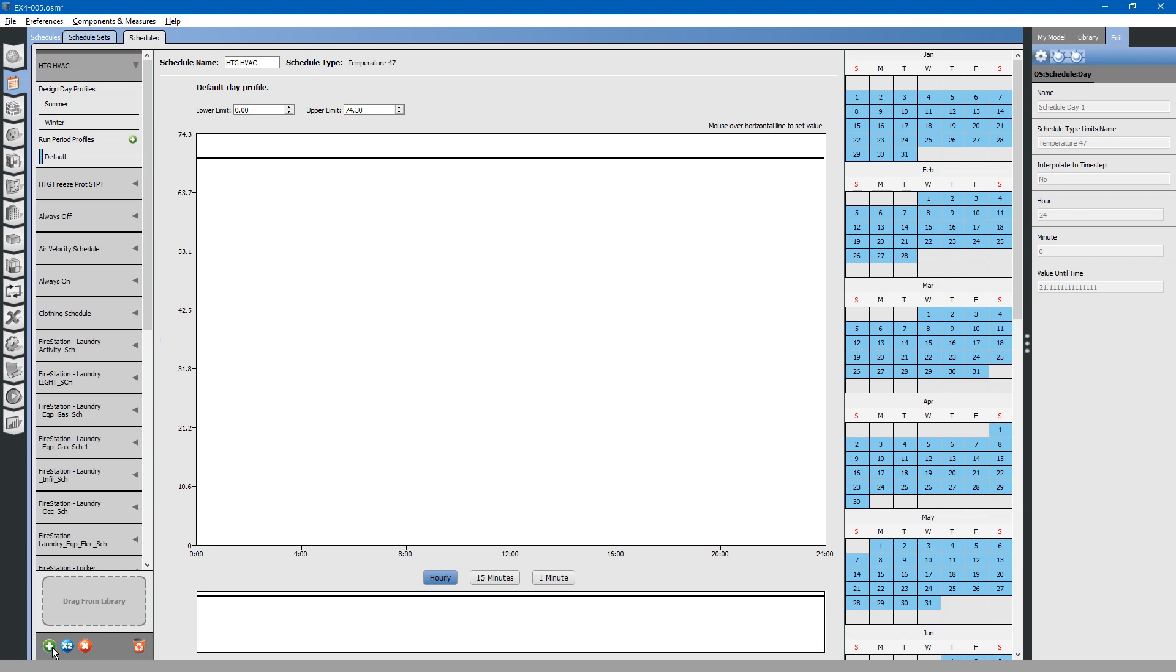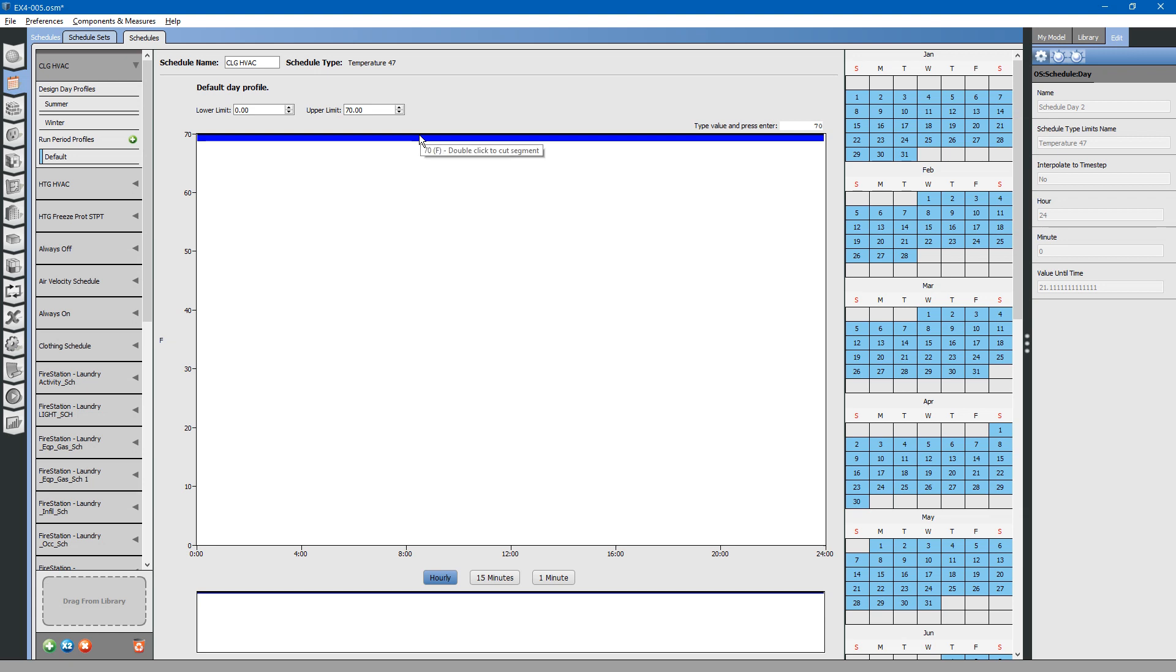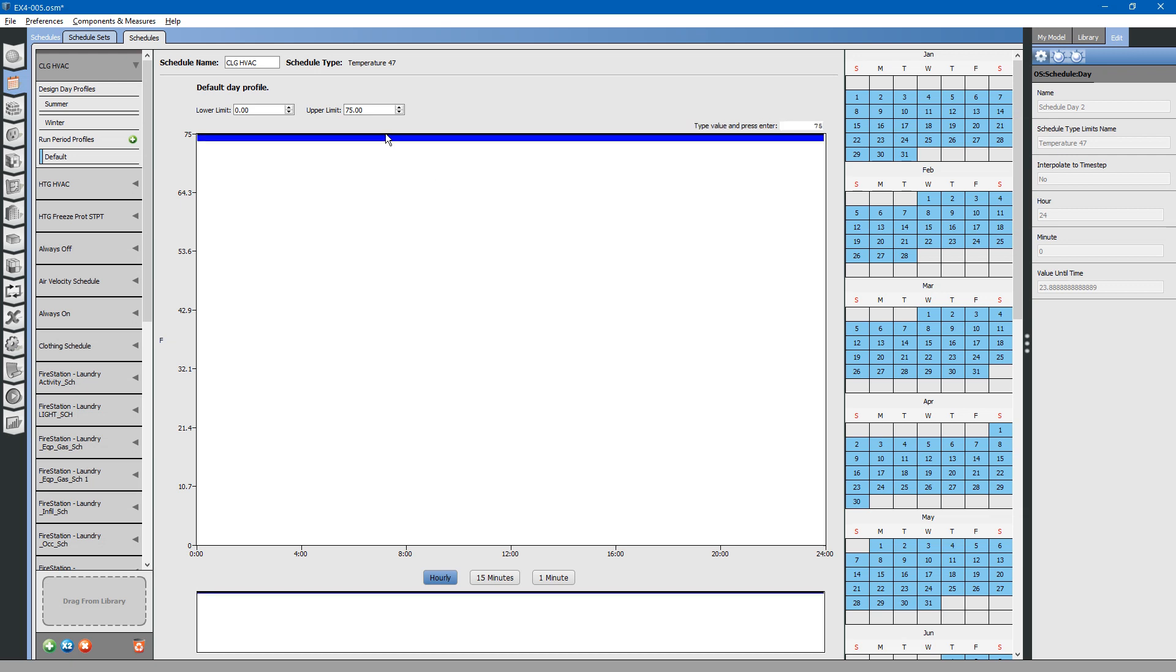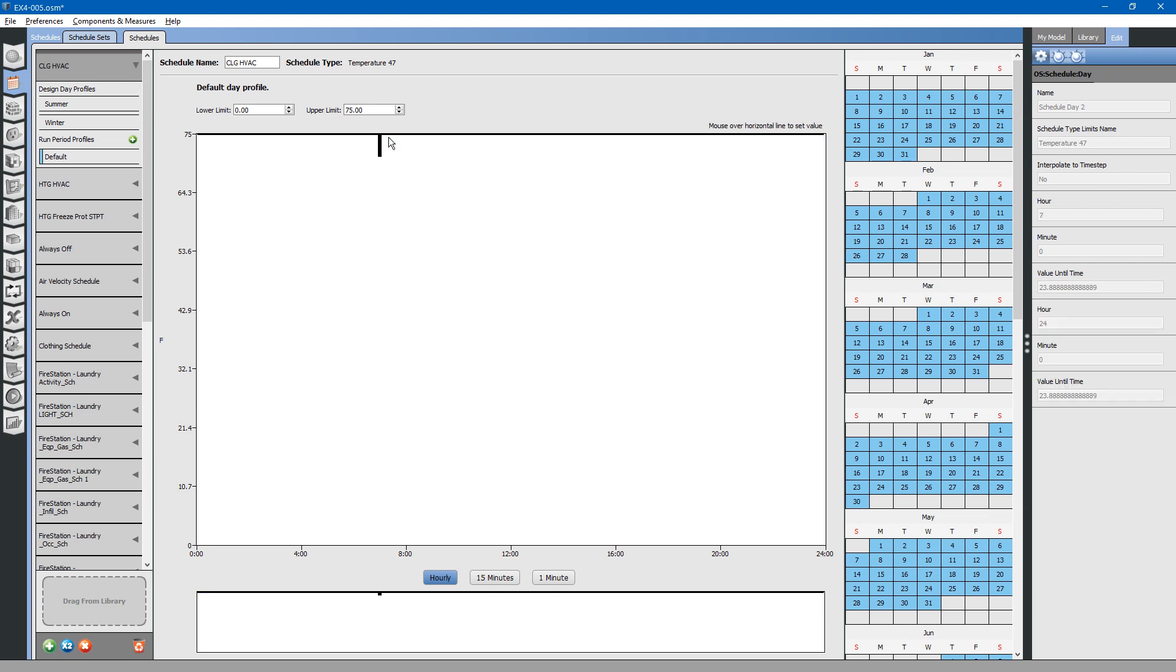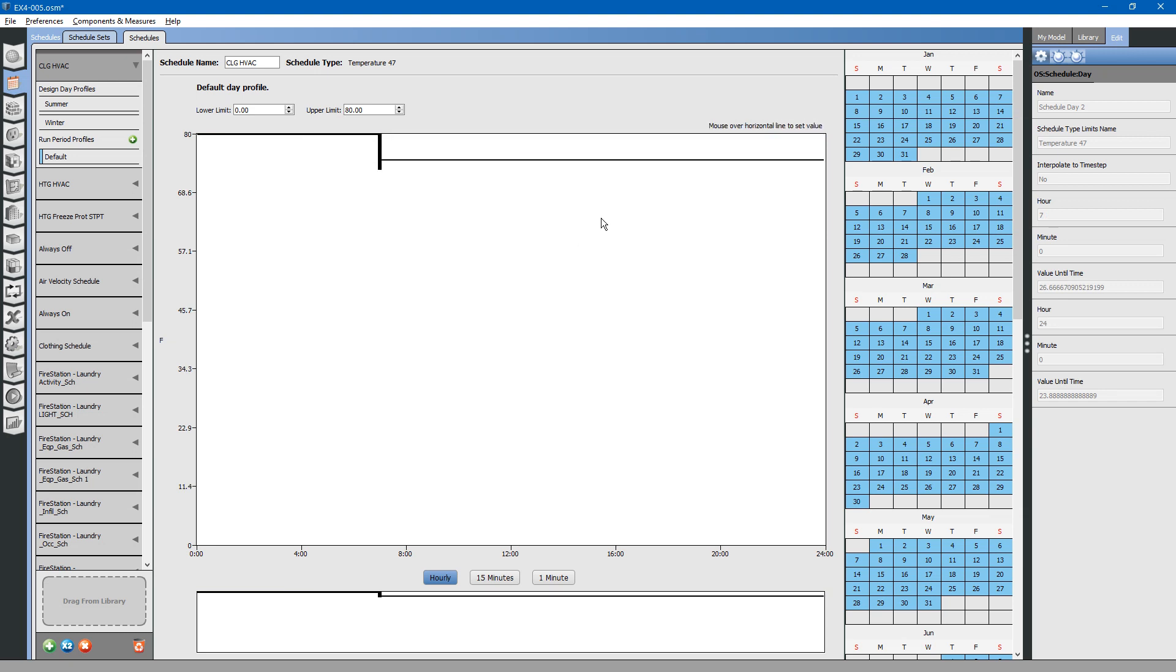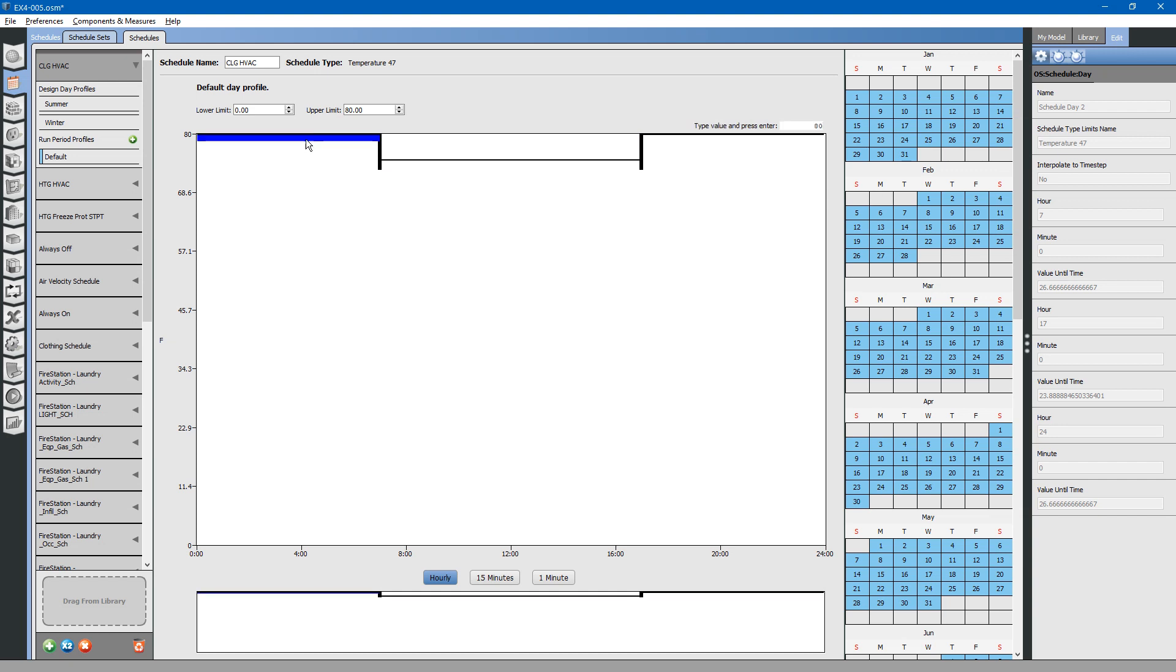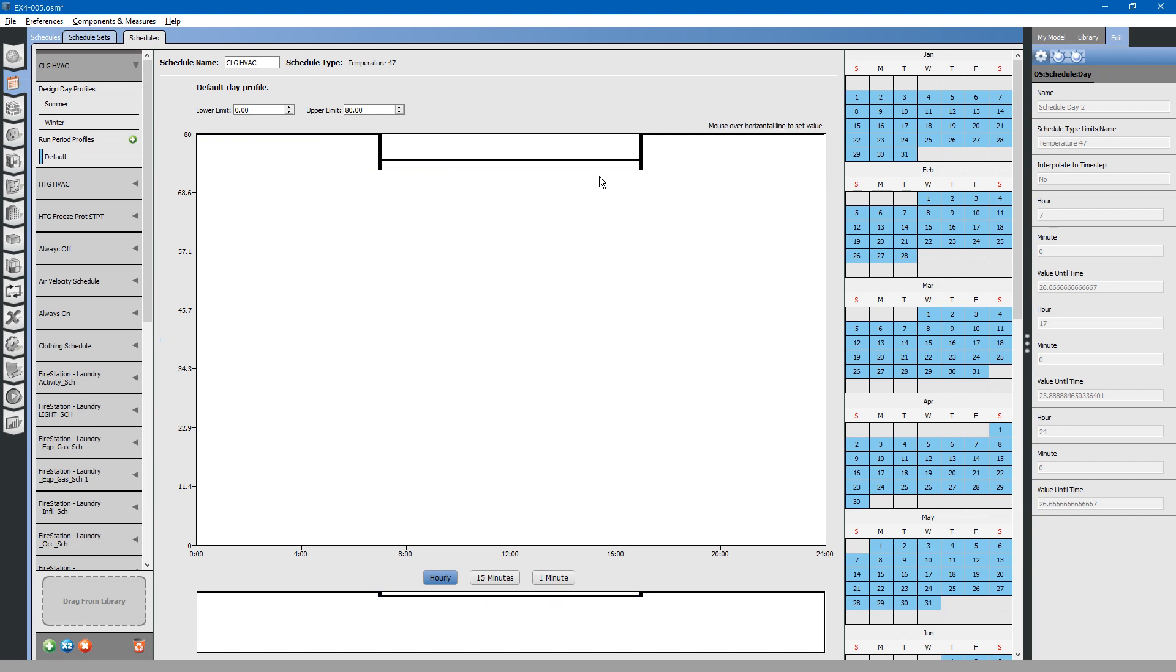Let us create another schedule, but let us copy this schedule. Push the times 2 button. We will call this cooling HVAC. Change this value to 75. We will say that cooling has a night setback just to save energy. Double-click on the line to create a break. Hover over the morning hours and type in 80. Double-click on the other side of the line to create a break. Hover over it and type 80. This sets the thermostat back during the night time so that the building is not being actively cooled. That way, during the daytime, the building is actively cooled and the cooling system shuts off at night time.